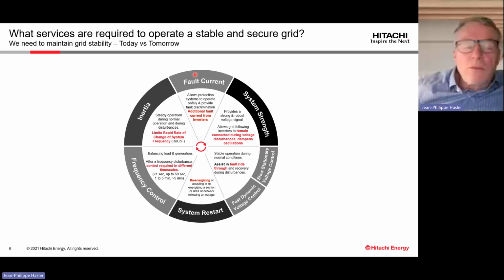Just to summarize the services that we have to provide now with the STATCOM, maybe I start from the top one. It's fault current, which is what happens during a fault condition. In the past, the fault current was provided by generators. But normally wind farms, especially the ones we have nowadays, of course provide some fault current, but not always, or at a reduced level. And one task for the STATCOM now is to improve the fault current. That's the main purpose: to ensure that the protection system, which is based on the short circuit current, will work as it did before.